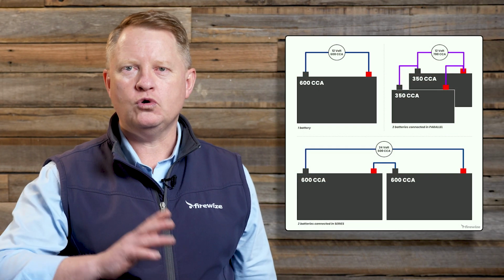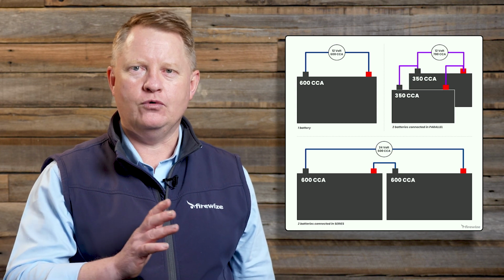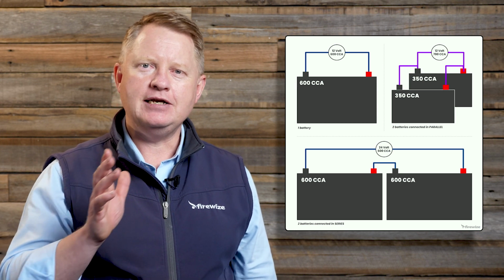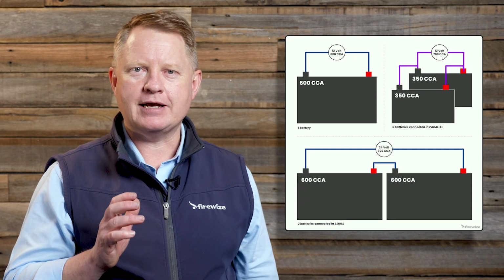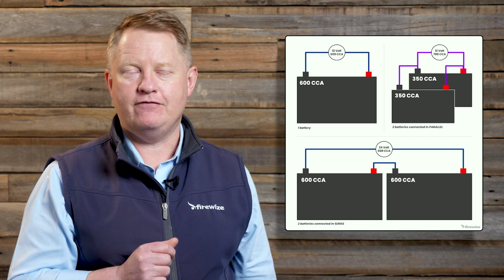Modern diesel-driven firewater pumps are also fitted with two sets of batteries in either a 12-volt or 24-volt configuration. The primary battery is for an automatic engine start application, and a secondary battery is for manual backup start or automatic start in the event of the primary battery failure. Older diesel-driven fire pump sets may have only been fitted with a single battery for engine start applications, with a secondary control battery used to operate the pump controller in the event of mains fail.